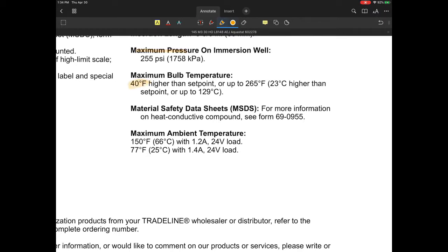Let's see, max pressure. I don't think that's ever going to come into play. 255 psi, I don't see that ever being an issue. The max bulb temp, 40 degrees higher than the set point, so they're saying up to 265 degrees. There again, I don't think you're ever going to run into that. But where it could become a problem is if somebody were to take a torch and heat that immersion well or the sensing bulb up. I don't know why anybody would do that, but I could see where that could be a problem. Again, very rare that it would ever be an issue.